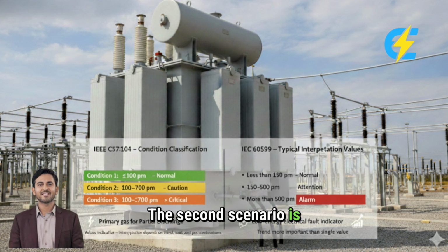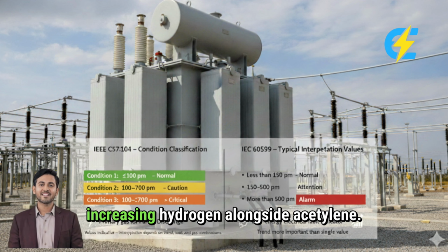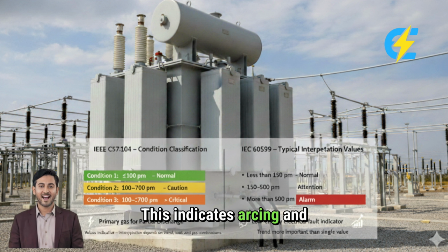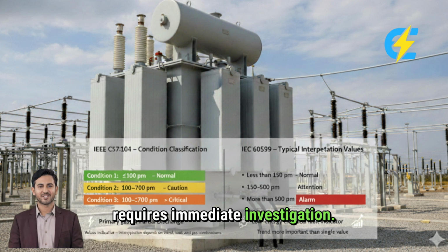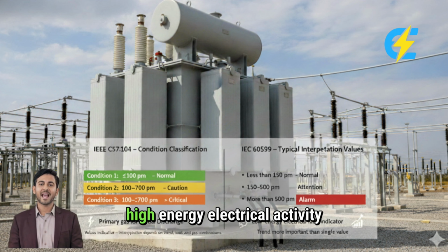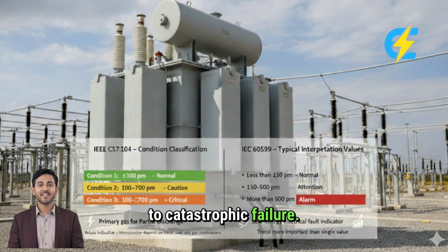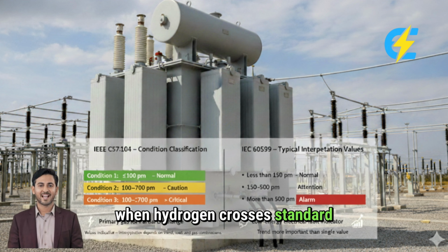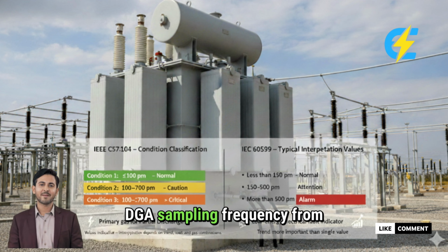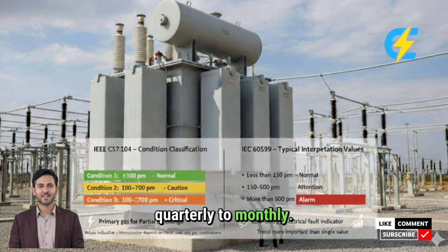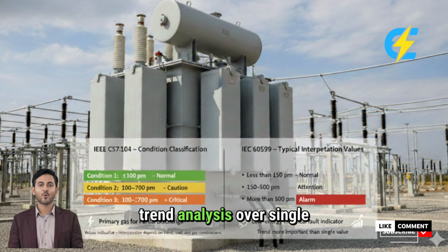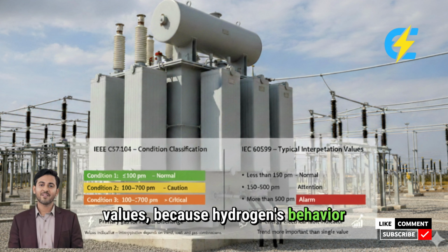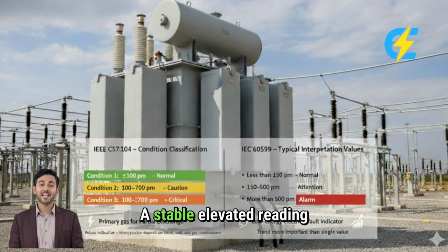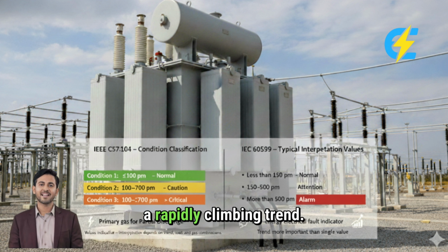The second scenario is far more serious. Rapidly increasing hydrogen alongside acetylene. This is serious. This indicates arcing and requires immediate investigation. When you see this combination, you're looking at high energy electrical activity that can quickly escalate to catastrophic failure. The key engineering actions when hydrogen crosses standard limits include increasing your DGA sampling frequency from quarterly to monthly. You need to prioritize trend analysis over single values, because hydrogen's behavior over time tells the real story. A stable elevated reading is very different from a rapidly climbing trend.